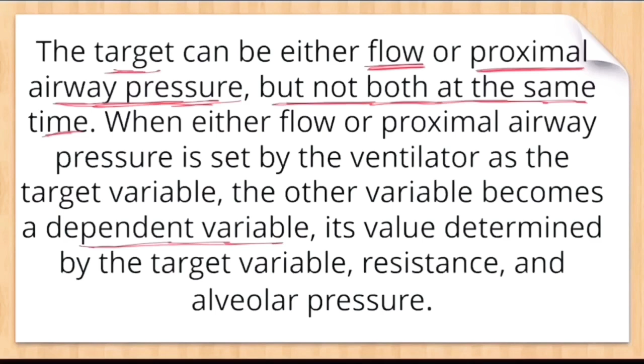Now flow target. With flow target, flow is selected as an independent variable. Okay, so the flow will be independent variable. The ventilator simply delivers the flow as set by the provider. Therefore, the proximal airway pressure becomes dependent on flow, resistance, and alveolar pressure. Like I was discussing that equation, Q is equal to proximal airway pressure minus alveolar airway pressure divided by resistance. Okay, so if you have kept the Q as the independent variable, the other variables like proximal airway pressure, alveolar airway pressure, and the resistance will be dependent on this flow.